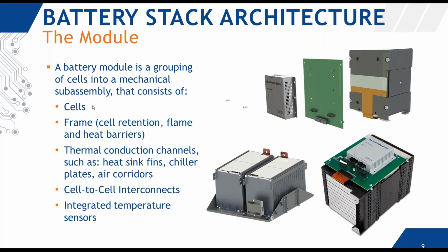And so when we assemble those into a module, UL 1973 recognizes a module as a mechanical subassembly. And so that will also contain among the cells a frame, and that frame can hold the cells, but it also offers some flame and heat barrier, which is important for managing thermal propagation. We can also have the thermal conduction channels in place. So those would be things like heat sinks, chiller plates, air corridors for forced air cooling. It'll also have the cell-to-cell interconnects for how to wire the high current path, as well as they usually integrate the temperature sensors right inside the module.